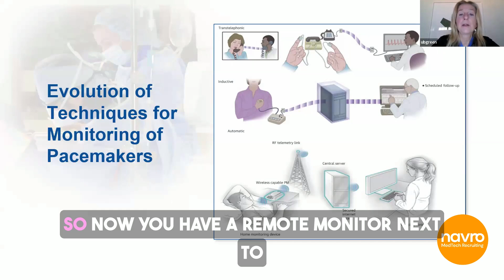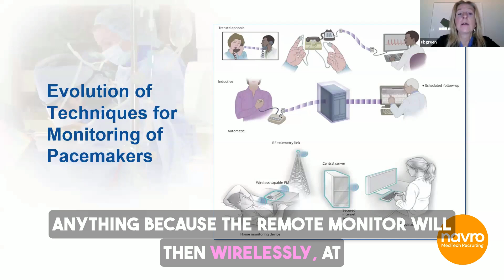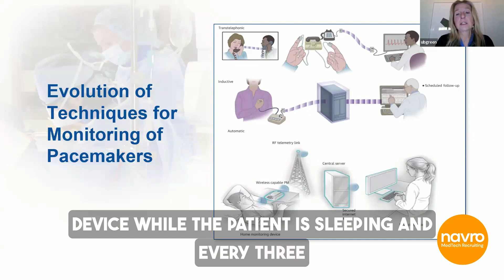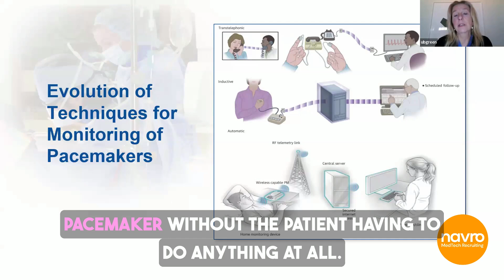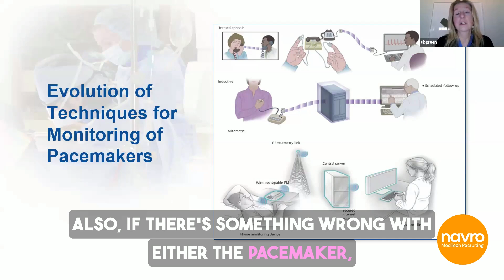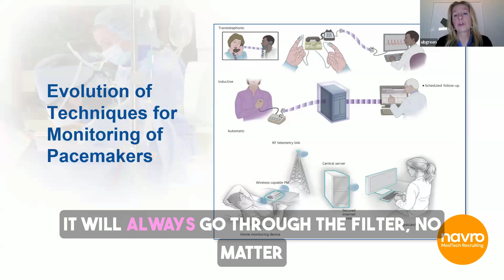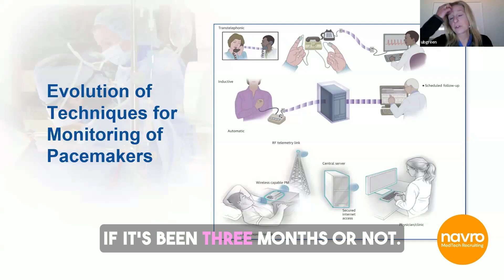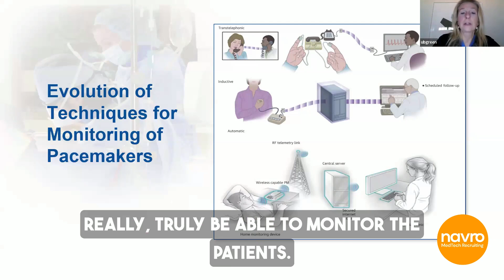So the next thing that happened was that it became completely wireless. So now you have a remote monitor next to your bed, and you really don't have to do anything, because the remote monitor will then wirelessly at about 2 o'clock in the morning go check the device while the patient is sleeping. And every 3 months go through this secured filter to us, and we would see everything that goes on with the pacemaker without the patient having to do anything at all. Also, if there's something wrong with either the pacemaker, if the patient is having heart rhythm problems, then it will always go through the filter, no matter if it's been 3 months or not. So this way is a way for us to really truly be able to monitor the patients.